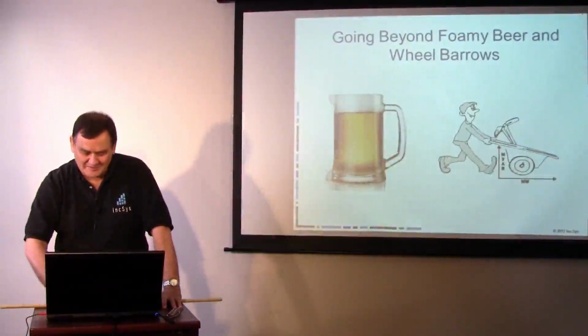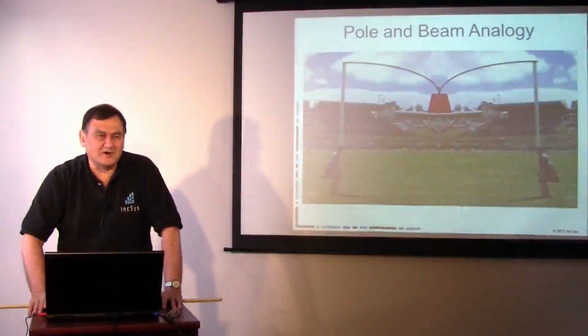So we have a proposal, and we call it the pole and beam analogy. The generators are analogous to these cable lifters, and they are lifting these poles. The generators have a megavar contribution, and as they lift those poles—let's say it's a 230 kV system—you want that generator to keep that megavar right at 230 kV. That's analogous to the cable lifter keeping his pole right at, say, 23 feet.